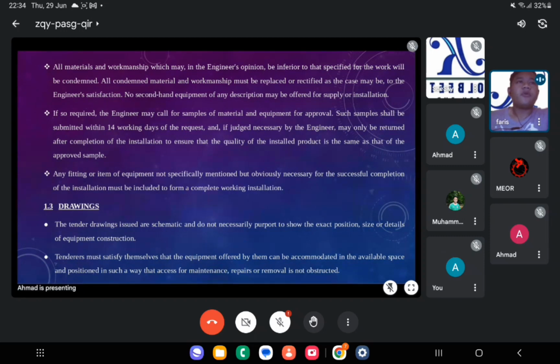Any fitting or item of equipment not specifically mentioned but obviously necessary for the successful completion of the installation must be included to form a complete working installation. 1.3 Drawings. The tender drawings issued are schematic and do not necessarily purport to show the exact position, size or details of equipment construction. Tenderers must satisfy themselves that the equipment offered by them can be accommodated in the available space and positioned in such a way that access for maintenance, repairs, or removal is not obstructed.